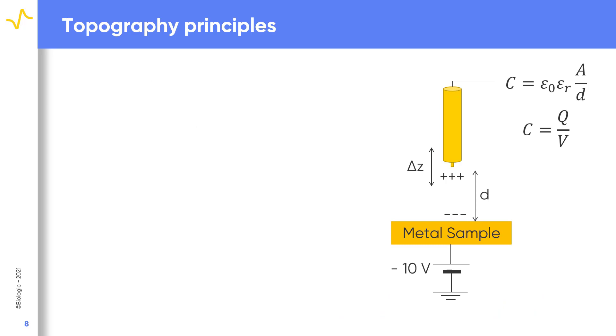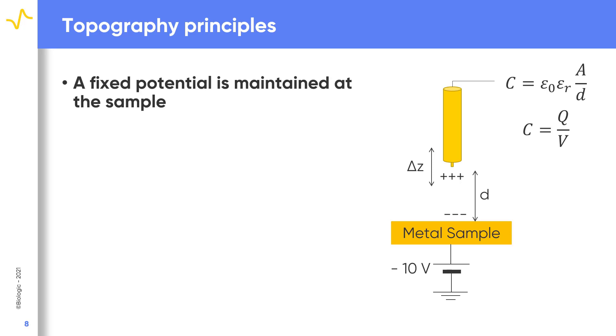In the standard SKP measurement, in order to measure the contact potential difference, the probe and the sample are connected and a variable bias is applied between them. In the SKP topography measurement, however, a constant potential is applied to the sample. This potential is typically minus 10 volts, although it can be set by the user anywhere from minus 10 to 10 volts. A different value would be used if the sample could be easily damaged by the high voltage applied.